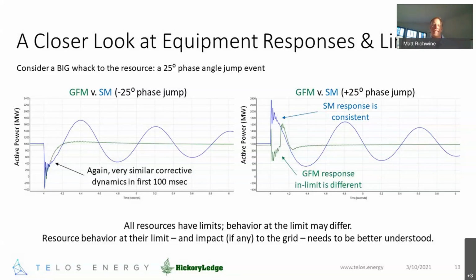Where it starts to get interesting is on the right, where we look at the same phase jump but in the opposite direction, such that the response we'd expect is an increase in active power transiently. You can see the synchronous machine, in the blue line, does that. The scale here is that the power immediately after the event nearly doubles from what it was doing, which is well over the rating of the machine that was modeled. That's something we expect, they have a high capability, a high ability to take that rotating kinetic energy from the rotor and move it to the grid. They have a great ability to do that.